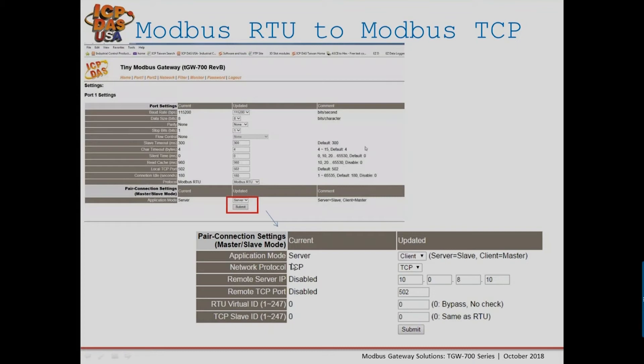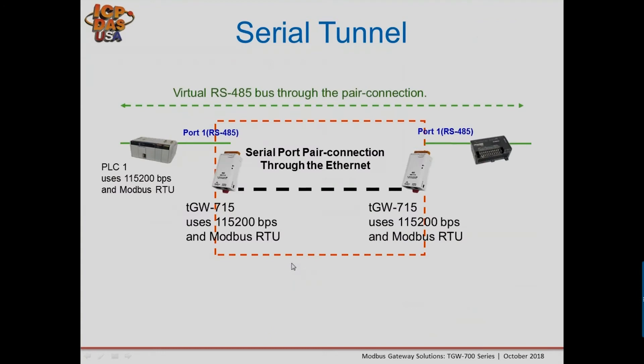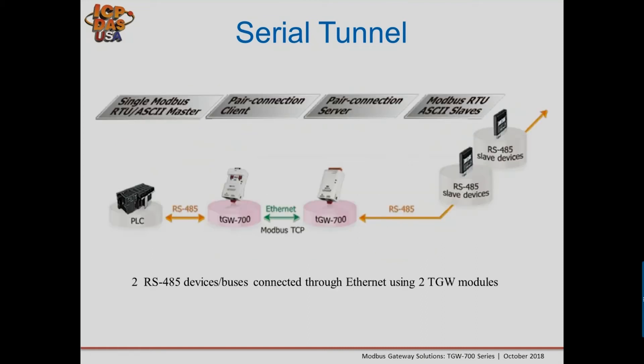The serial tunnel application connects a PLC or any RS-485 device on one end, through an Ethernet switch via two TGW modules, with data passed to the RS-485 bus on the other side. This is ideal for office buildings, large factories, or even inter-city locations. It also supports Modbus RTU ASCII protocol and allows different baud rates at each end.